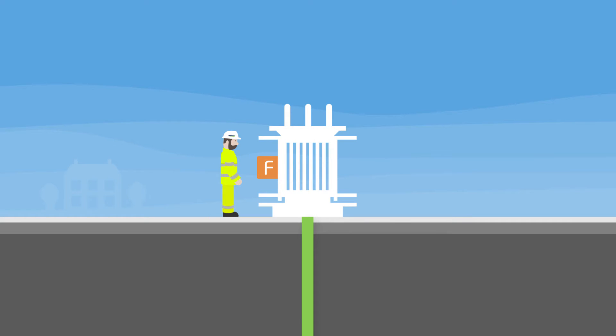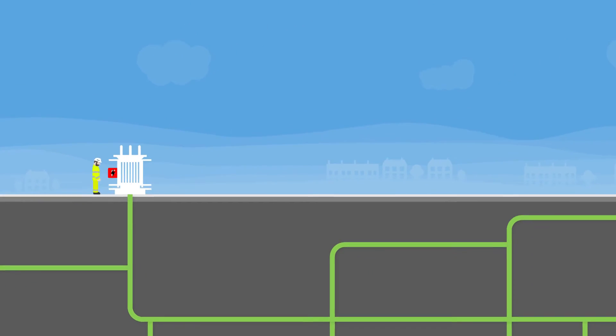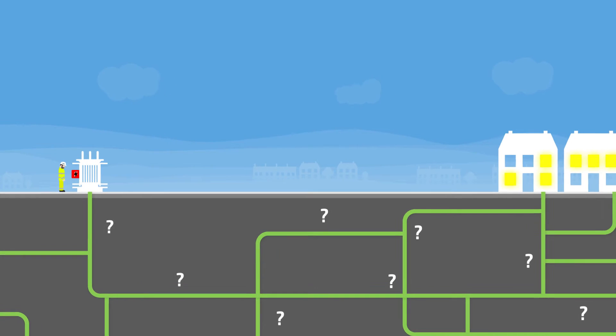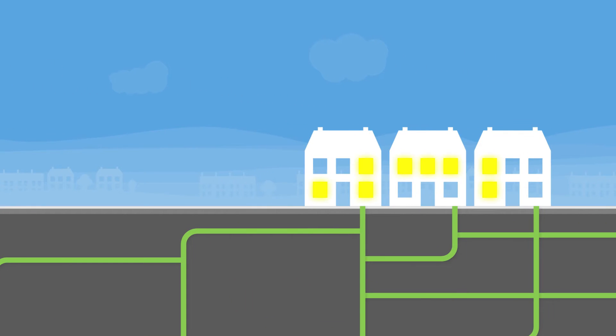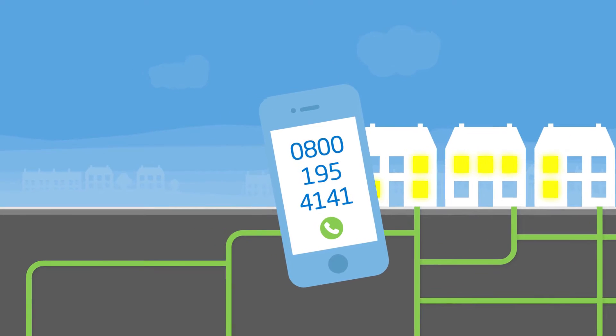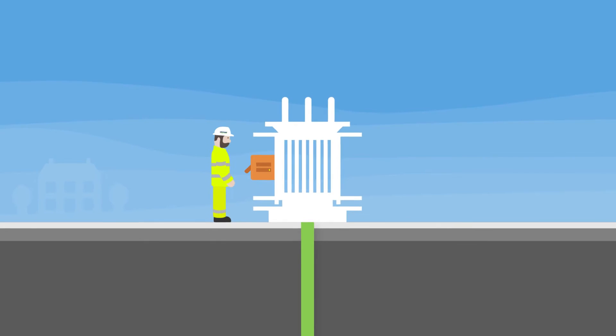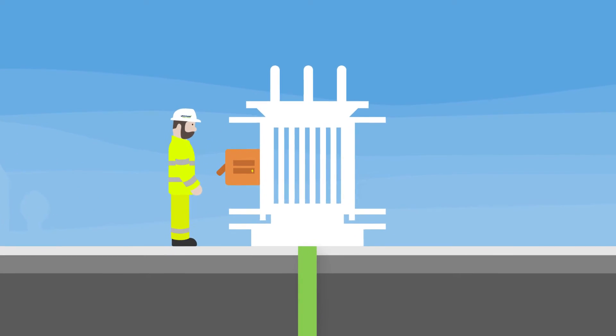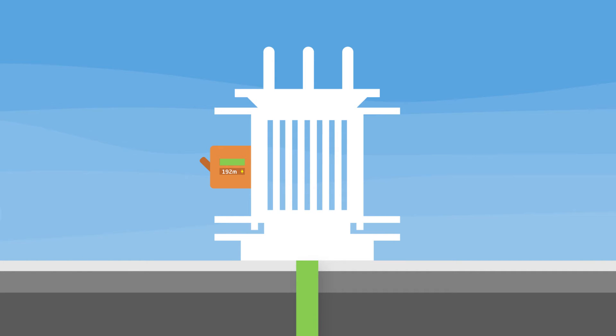But if it's a transient fault, the fault could occur again, and it can be difficult to tell which part of the underground cable needs digging up and fixing. If your power goes off repeatedly, rather than waiting for you to tell us and having to go back to the substation to replace the fuse again, we can install sophisticated switches in place of a normal fuse. This helps us restore your power quickly and safely, whilst helping us identify where the fault is without an engineer having to go back to the substation.